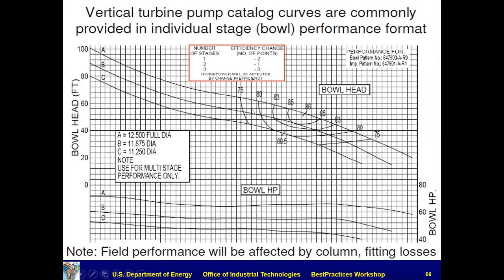So from these numbers, if you have just 1 stage, you have to deduct 2 percentage points. If you have 2 stages, you deduct 1 percentage point. And if you have 3 or more stages, you don't have to deduct any efficiency points. So it's kind of interesting. If you're working with a vertical turbine, just be real careful to read whether it's a total for the system or whether it's just per bowl. Because see, this is the horsepower per bowl. So if you had 3 bowls, you might be up here around 60 horsepower. You'd have to have a 200 horsepower motor. If you had 1, you could get by with a 75 horsepower motor.